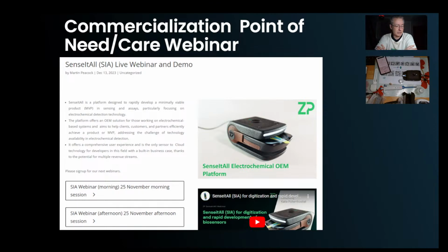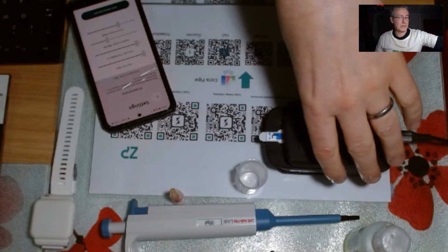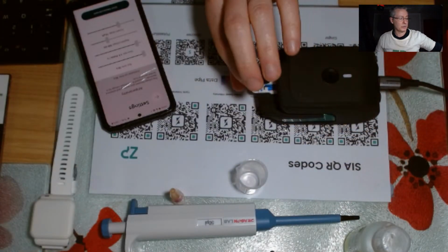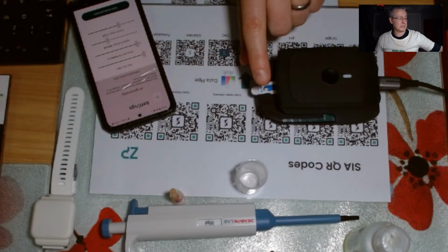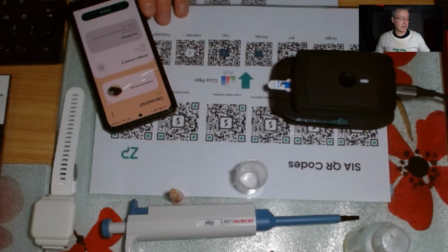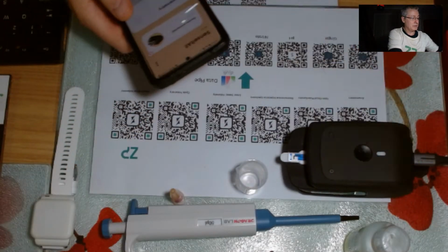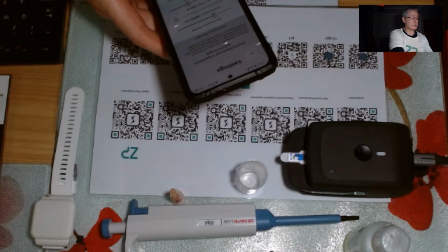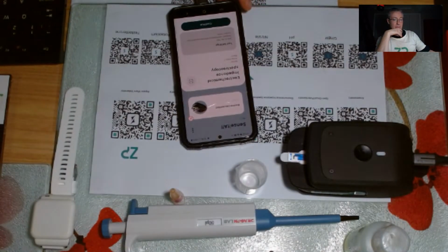If you are interested in making point-of-care diagnostics, there's two form factors that we get quite heavily involved with at ZP. Point-of-care diagnostics, so I would describe this as a kind of point-of-care diagnostic. You've got a sensor, you've got a potentiostat. In this particular case, we can drive this system using an app. So if I want to do something like impedance spectroscopy, for example, I can scan the impedance spectroscopy. I've got all my settings available to me. So I would describe that as a very point-of-care application.